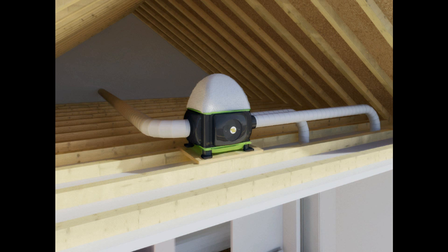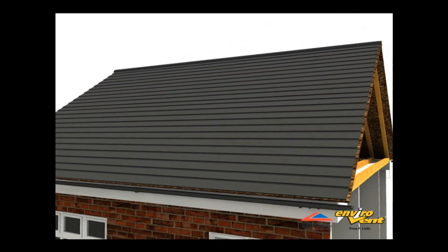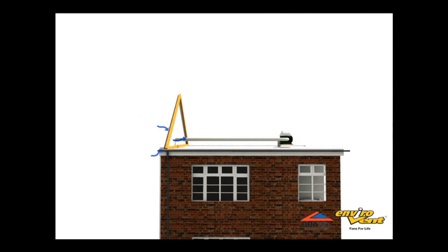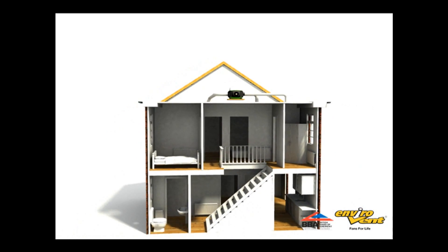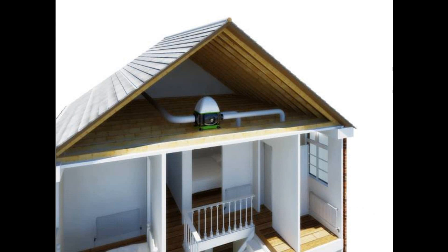When the loft temperature exceeds 25 degrees, the unit automatically detects this and activates a damper that switches the air supply from inside the loft space to the cooler air from outside the property. The result is all year round whole house ventilation, with fresh filtered air introduced into the property in the most energy efficient way possible.